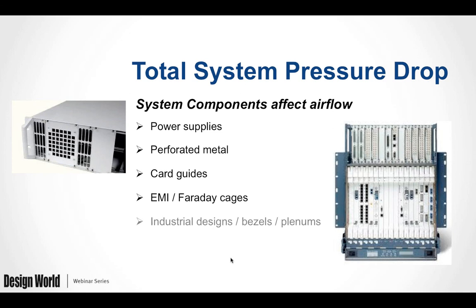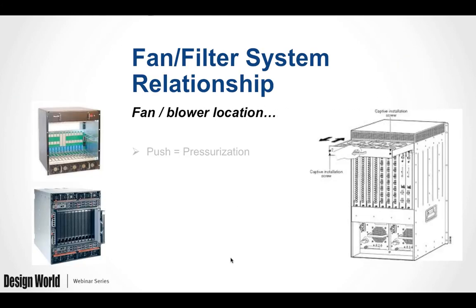Thermal analysis software packages are used to simulate equipment thermal characteristics and calculate the effects of less restrictive and more restrictive air filter media on overall system pressure drop. Note that all physical components contained in a chassis impede airflow effectiveness to varying degrees. Air filters are no exception but can be custom configured to match the airflow requirements of the specific application and deliver the most effective dust capturing at the lowest pressure drop. Forced air system designs use three popular cooling configurations.